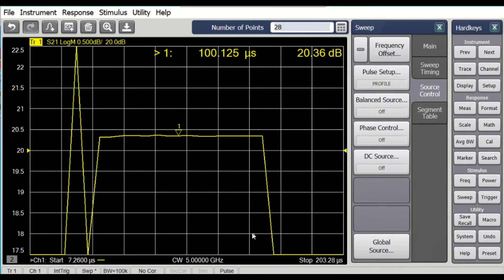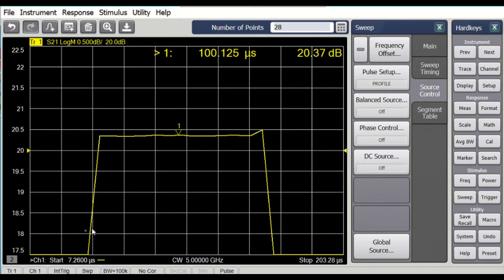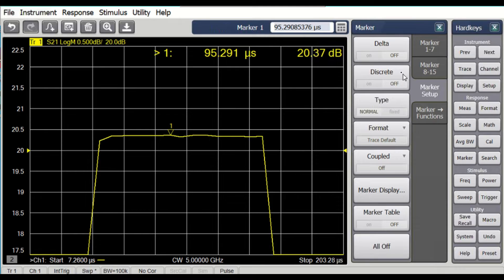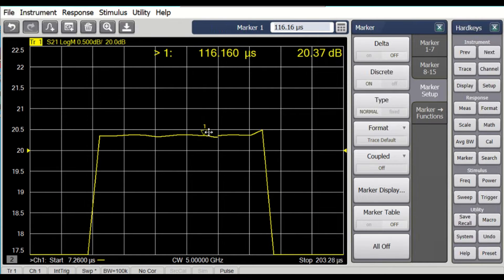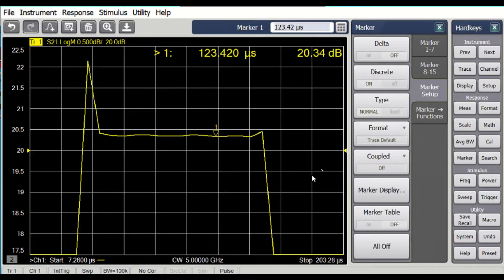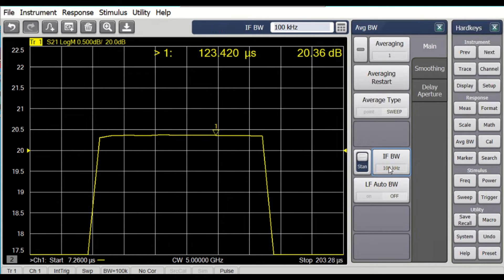It automatically sets the pulse to be in the middle 50% of the sweep — 25% below, 25% above. Now we have many fewer points. I can see the exact points by making the marker a discrete marker, which forces the marker to land exactly on the measured points. We can see that these points are at a 7.26 microsecond increment — 101, 108, 116, 123 — those increments are set precisely by the time it takes to do the IF bandwidth. We can use different IF bandwidths to get different time increments.